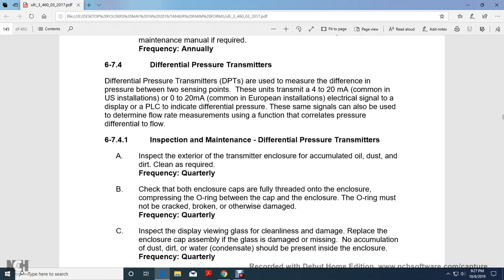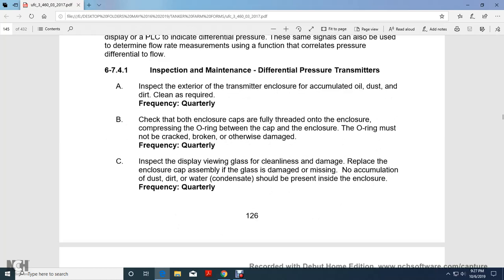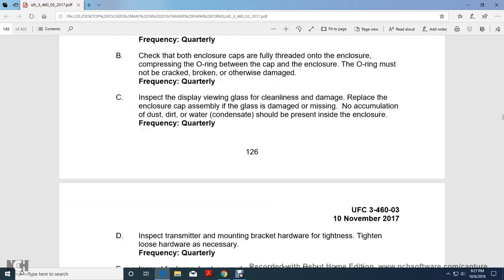Inspection and maintenance of the differential pressure transmitter. Inspect the exterior of the transmitter enclosure for accumulated oil, dust and dirt, and clean if required. Quarterly, check that both enclosure caps are fully threaded, compressing the O-ring between the cap and the enclosure. The O-ring must not be cracked, broken, or otherwise damaged. Quarterly, inspect the display and viewing glass for cleanliness and damage, and replace the enclosure cap assembly if the glass is damaged or missing. No accumulation of dust or dirt. Water condensation should not be present inside the enclosure.